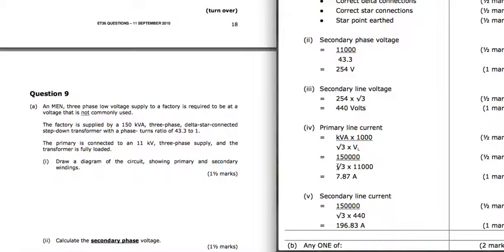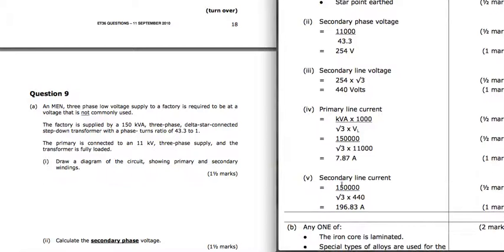The only problem with this calculation, you need to either put this in brackets on the bottom there, or find the answer to that, and then do 150,000 divided by that. Don't do straightforward 150,000 divided by √3 times 11,000, because you won't get the correct answer. So if you do it correctly, put some brackets there, we get 7.87 amps is our primary line current.